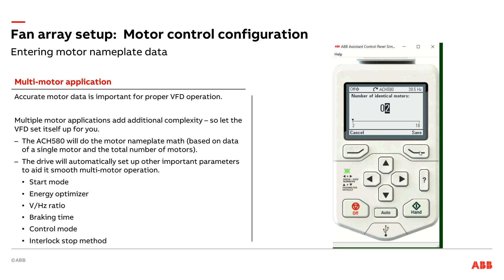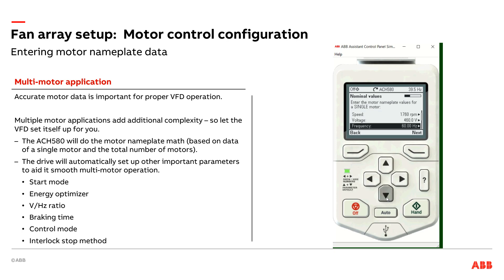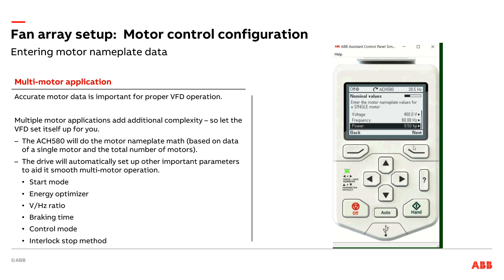For this example we're going to assume just two motors. I've got my two motors, hit Next. Now I'm going to enter the nameplate values for a single motor — what is one motor's rating? I'm playing on my little demo case here so it's a small drive. Just for fun, we're going to say it is a half-amp motor. So both of my motors are half-amp each. I can enter the speed — 1760 RPM — and the voltage at 460 volts. I can enter the frequency and also the horsepower. Let's say it is a half-horsepower motor. So each one is half-amp, half-horsepower — I'm letting the math be really easy today.